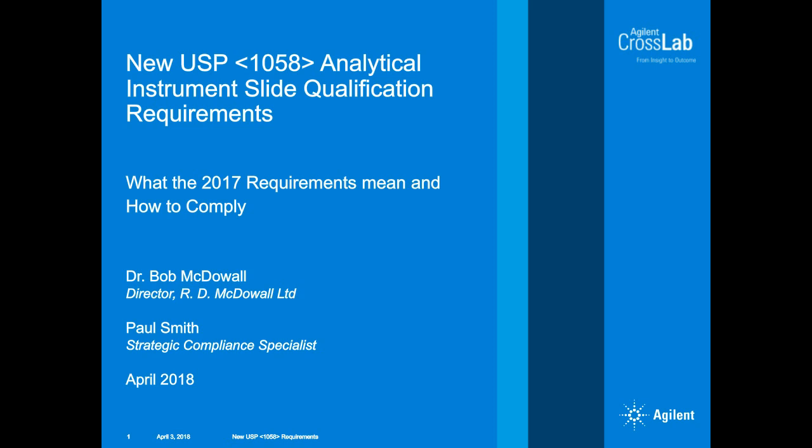So you cannot assume that I've just done an IQ and an OQ of the chromatography data system software. You have to have a user requirement specification, typically a configuration specification, and a traceability matrix, because this now comes under Annex 11, Clause 4.4, where you have to have traceability of requirements throughout the life cycle.